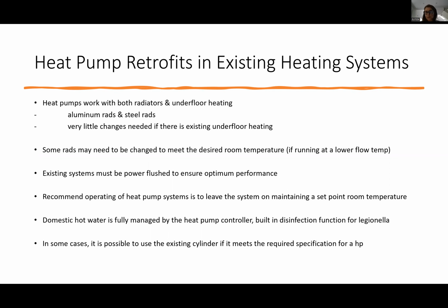The domestic hot water is fully managed by the heat pump controls, and it has a built-in disinfection function for Legionella. So it's a preset factory setting. Once a week, it'll bring the tank above 60 degrees and hold it there for 10 minutes. So there's no external controls required for domestic hot water production with heat pumps.